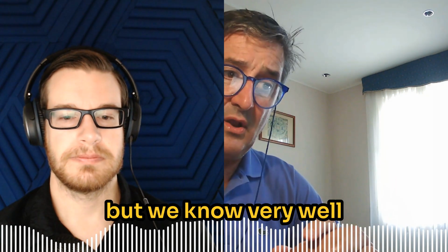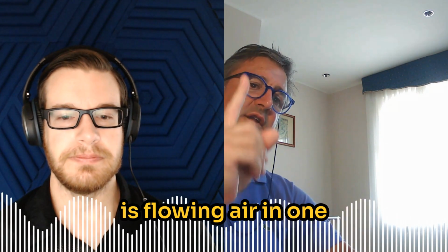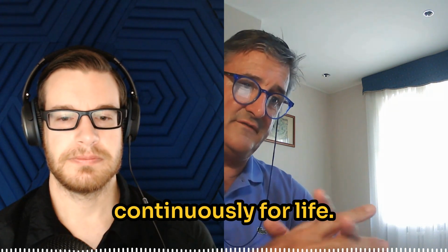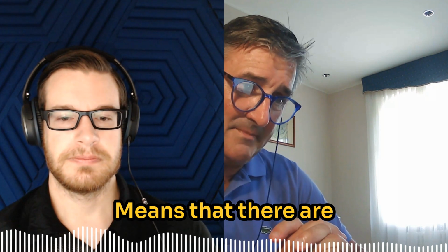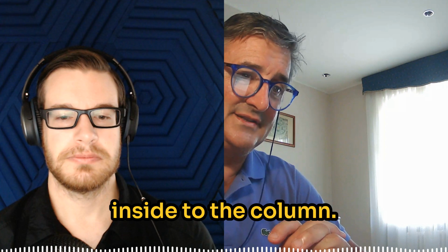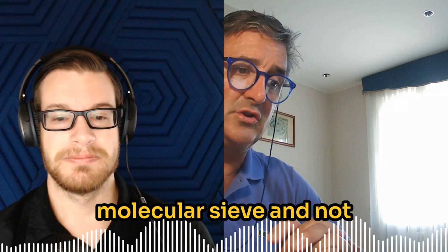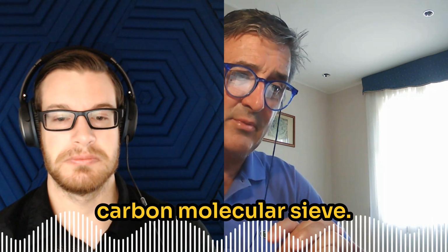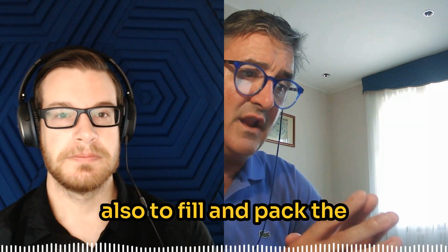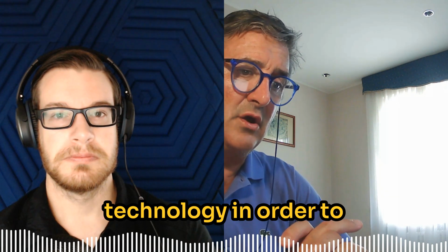It doesn't matter. But we know very well that the PSA technology is flowing air in one side and then nitrogen and air in the other side continuously for life. What does that mean? It means that there is the potential for carbon molecular sieve movement inside the column. And this is not good for the life of the carbon molecular sieve and not good for its efficiency.